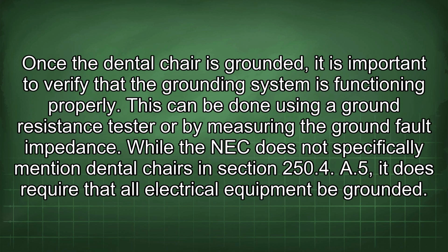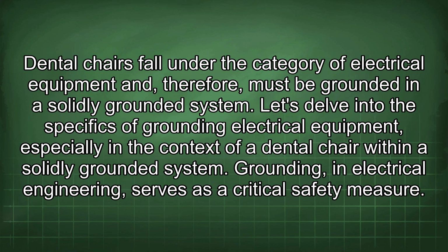Once the dental chair is grounded, it is important to verify that the grounding system is functioning properly. This can be done using a ground resistance tester or by measuring the ground fault impedance. While the NEC does not specifically mention dental chairs in section 250.4(A)(5), it does require that all electrical equipment be grounded. Dental chairs fall under the category of electrical equipment and, therefore, must be grounded in a solidly grounded system.